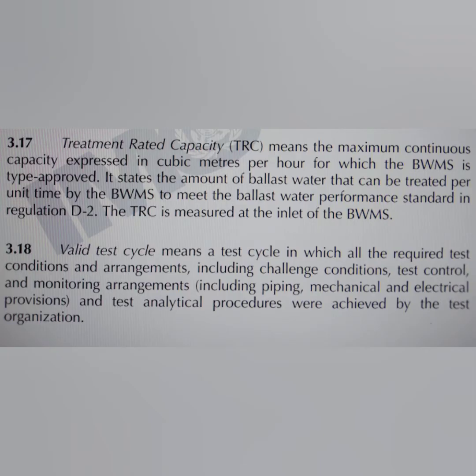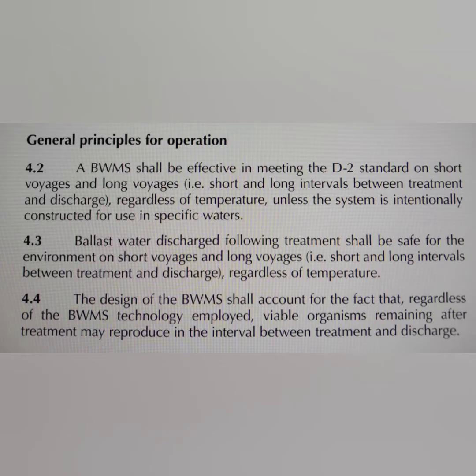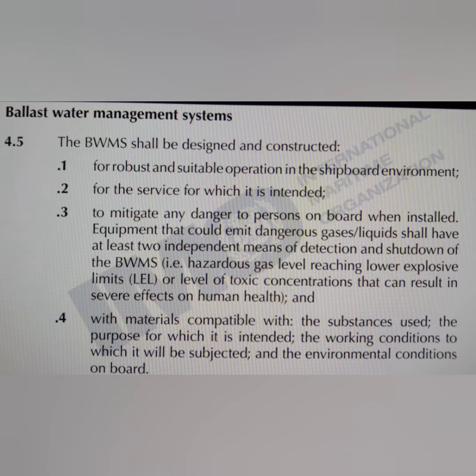Treatment rated capacity is the next definition. Based on the ship's design, there will be a certain amount of water that your ballast water treatment system can treat in a certain amount of time. That amount expressed in cubic meters per hour is your treatment rated capacity. Chapter 4 is technical specification, which talks about the general technical requirements a ballast water management system shall meet in order to obtain type approval, covering general principles for operation and system design and construction — basically providing guidelines for the manufacturer.